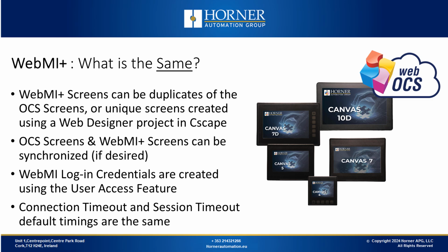If you decide to have your WebMI Plus screens as exact duplicates of what's running on the OCS screen, then you can choose to make the WebMI screens and the operator screens synchronized. So when the operator changes screens on the OCS, the WebMI Plus screens will also change, and vice versa. From a login credential standpoint, WebMI Plus also uses the user access feature for its credentials. The connection timeouts and the session timeout are also effectively the same for WebMI and WebMI Plus.